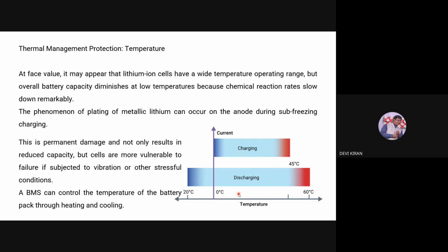For example, if the thermal range of the battery is between minus 20 degrees centigrade to 60 degrees centigrade, if it goes beyond 60 degrees centigrade, it automatically trips off the charging or discharging. Thermal management is very important because once it goes beyond thermal runaway, the entire battery can blast, so very serious measures are taken for thermal protection.